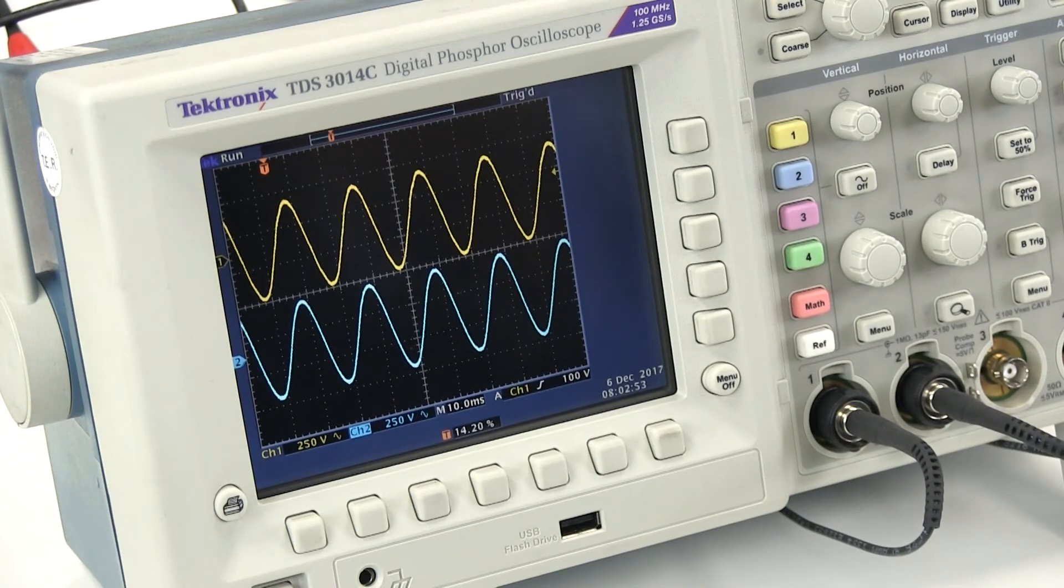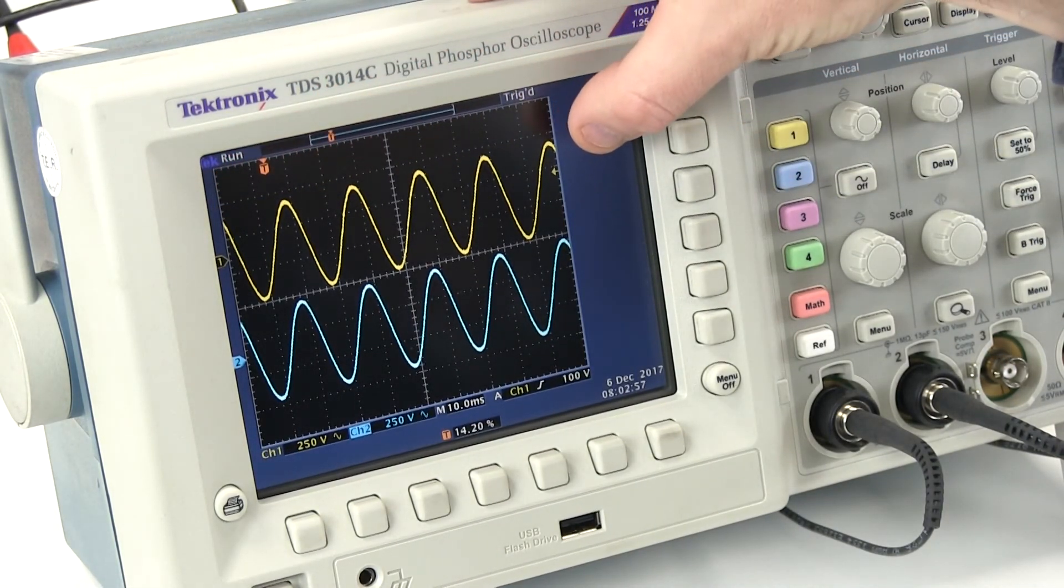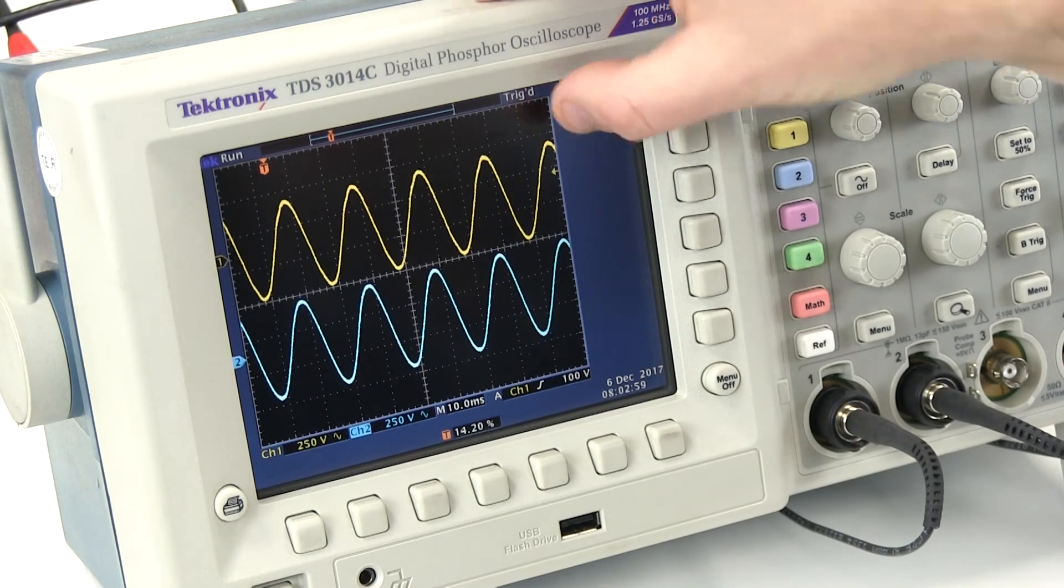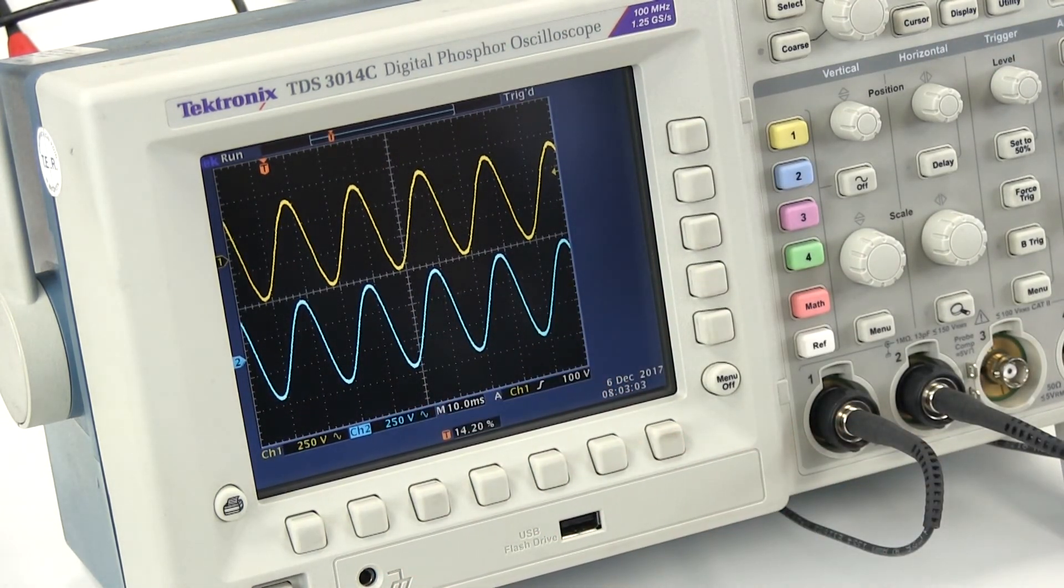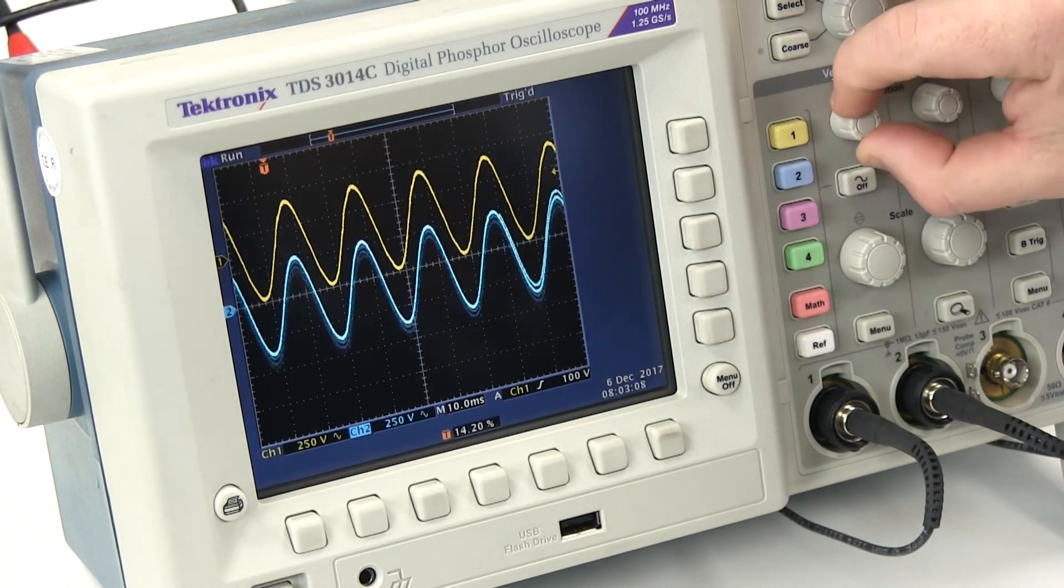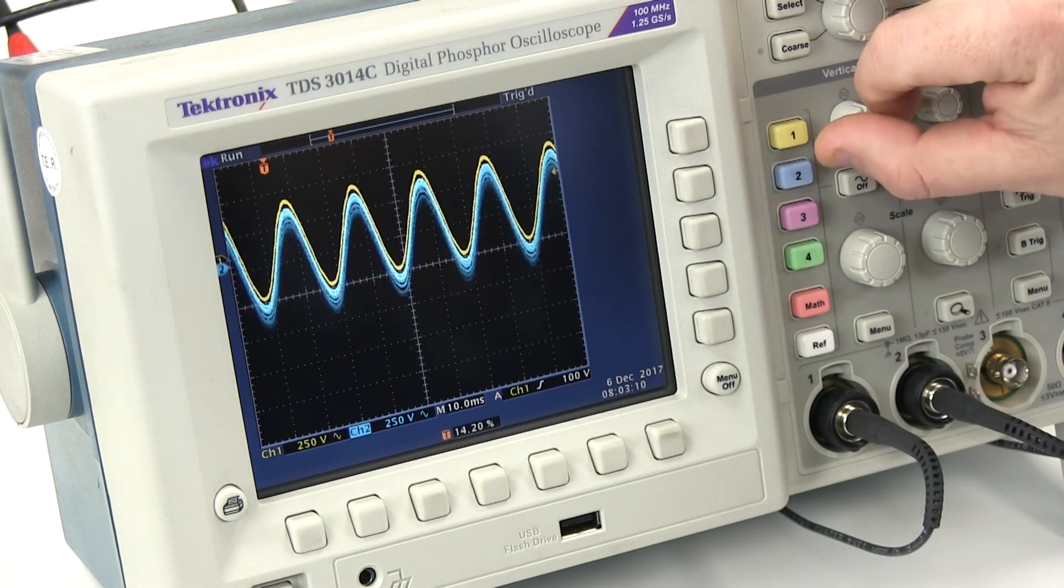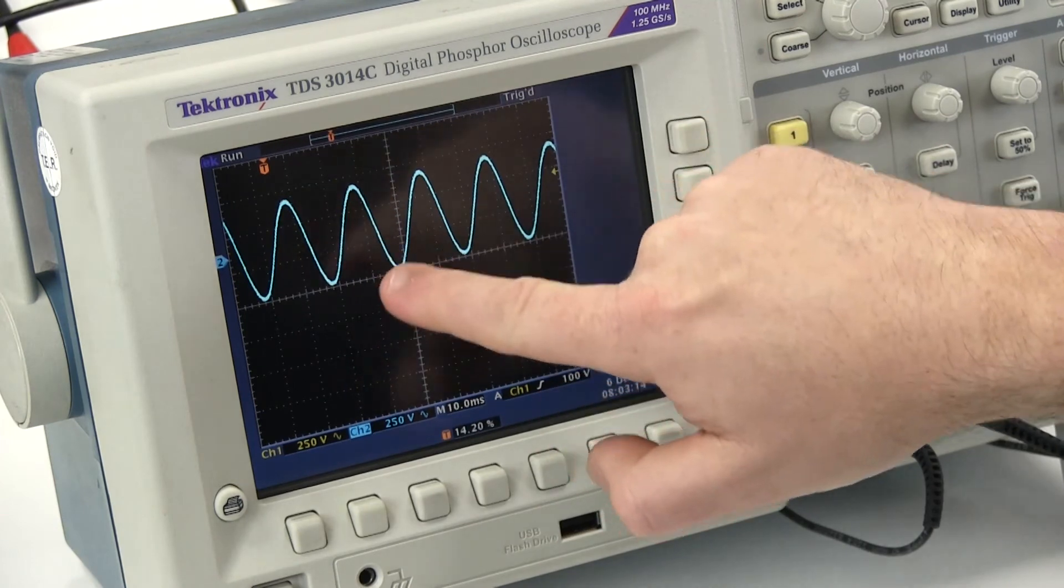If we take a look at the oscilloscope, the waveform across the top is the waveform supplying the bypass line. The waveform along the bottom is the waveform being produced by the inverter. If I move those two waveforms over one another, you can see clearly that they're practically identical and hence in phase with one another.